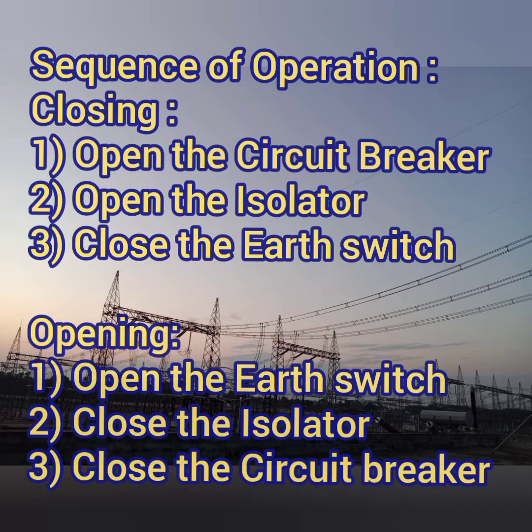In between the sequence of operation, there will be interlocks present. Because if any maloperation happened due to the operator or any remote section, in order to avoid maloperation these interlocks are present. If we need to close the earth switch, the isolator and breaker status should already be in an open condition as shown in our HMI or the BCUs.